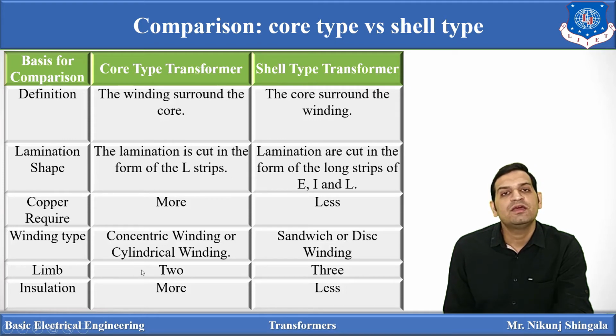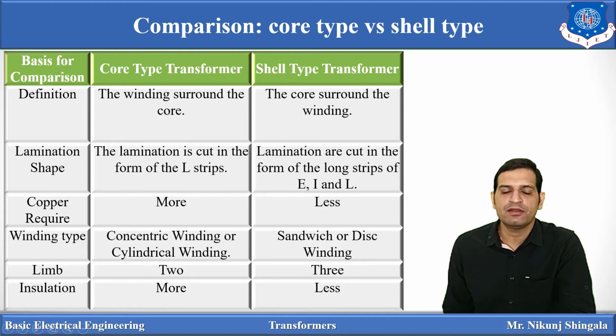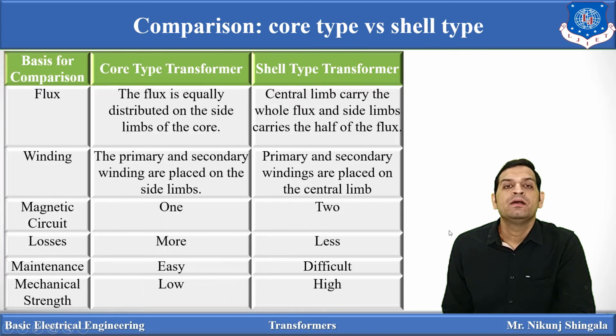Limbs: here there are two limbs. Here it consists of three limbs. It requires more insulation. Core type transformer requires more insulation and shell type transformer requires less insulation. Then flux. Flux is equally distributed on both the limbs of the core. Here main flux flows in the central limb, and in the side limbs half of the flux is flowing. Primary and secondary windings are placed on side limbs. Primary and secondary windings are placed on the central limb. It consists of one magnetic circuit. It consists of two magnetic circuits because it consists of three limbs.